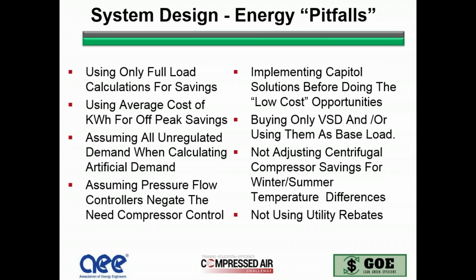Not adjusting centrifugal compressors for savings winter and summer. Since it's a dynamic machine, there's a big difference in what they actually produce because of the temperature difference, especially with the large climate changes. And not using utility rebates or government rebates. It's an important part for anybody that has efficiency.